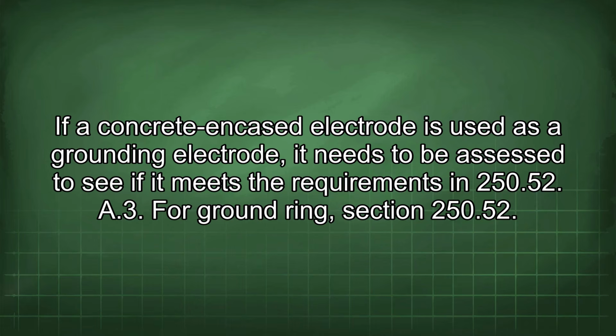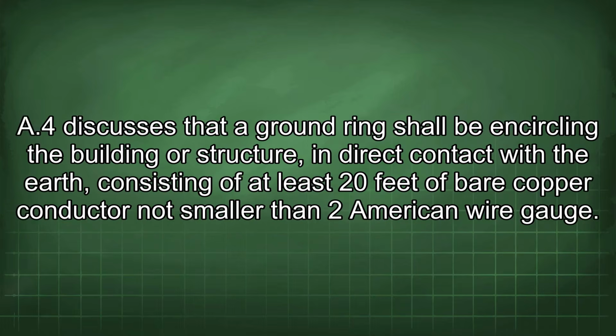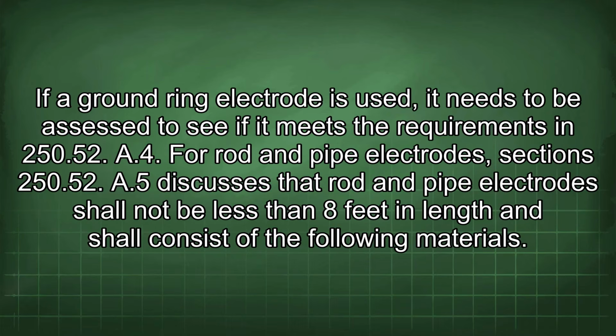(A)(3). For ground ring, Section 250.52(A)(4) discusses that a ground ring shall be encircling the building or structure in direct contact with the earth, consisting of at least 20 feet of bare copper conductor not smaller than 2 American wire gauge. If a ground ring electrode is used, it needs to be assessed to see if it meets the requirements in 250.52(A)(4).